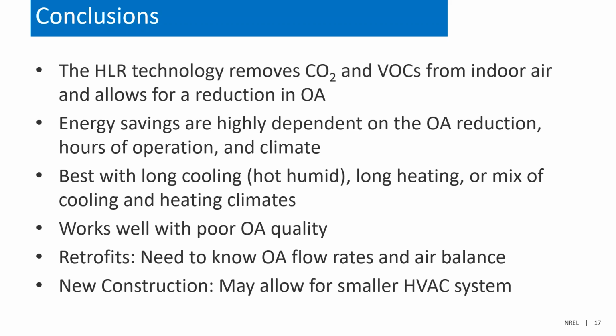If you're looking at a retrofit, you really need to know the outdoor airflow rates and the air balance in the buildings. And this was the biggest challenge we found in this whole demonstration, finding a building that we had confidence in the outdoor airflow rates. And we recommend, if you haven't done a measurement of your outdoor air and a test and balance of your system, doing that before you install this system if it's a retrofit.